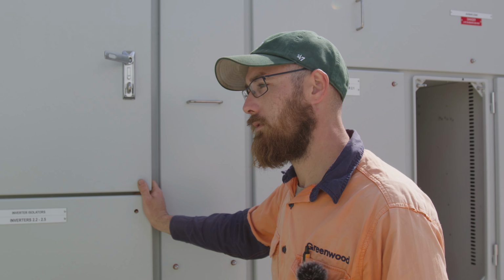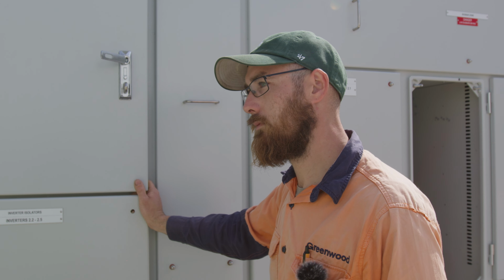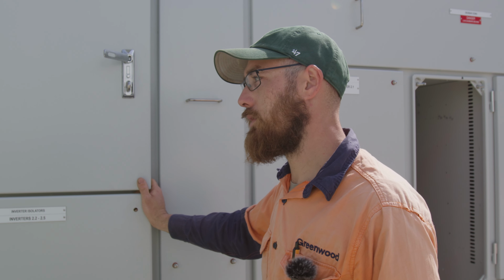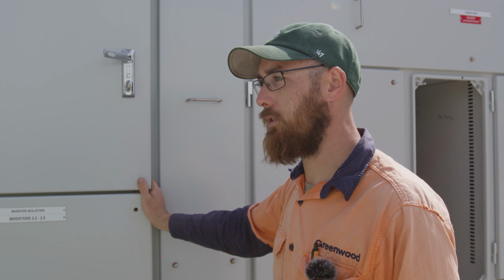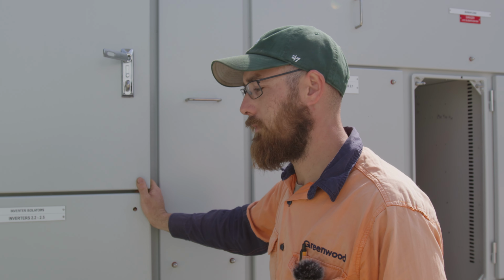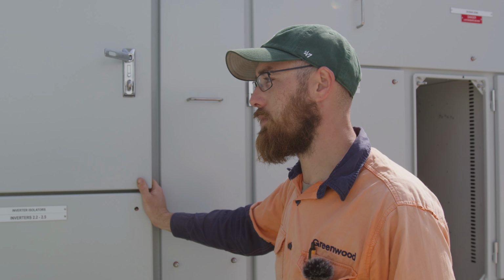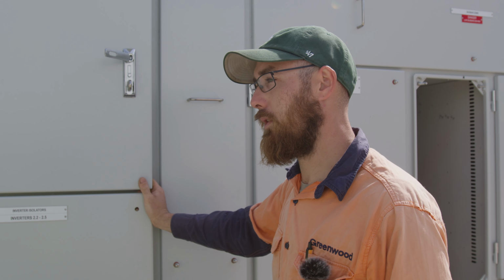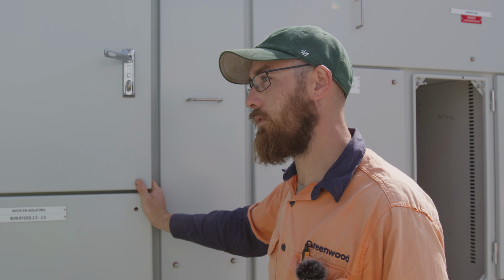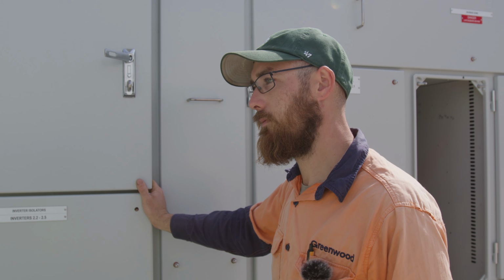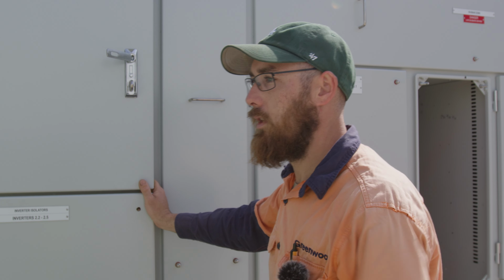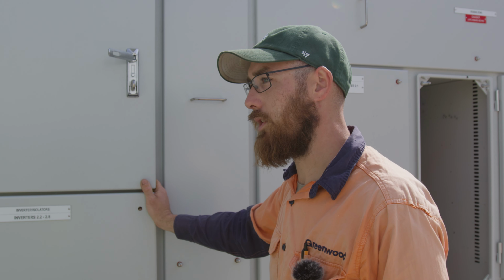That's fantastic. And what about from a cost perspective? Going up cable size is usually more expensive than going up cable temperature. Right, very interesting. And in this case, derating on the cables is inside the pits, where we have all of the inverters go through the same pits. So there is a pit behind this board that has all cabling for all 12 inverters go through it.